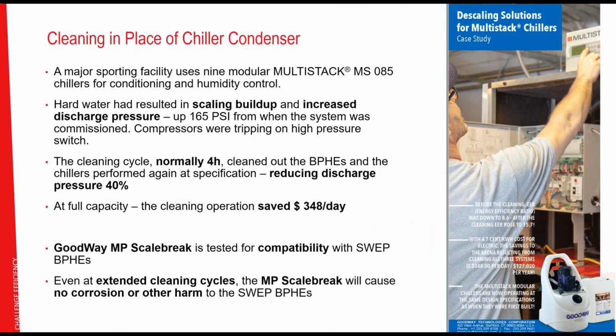One of the case stories that we did together was with a mutual customer, Multistack Chillers. And this case here was a sporting facility somewhere in the south, which had a Multistack MS85 chiller, or quite a lot of them. What they noticed was that the compressors were tripping on the high pressure switch. That's normally not the case. That shouldn't happen, right? So they did a measurement and they saw that the discharge pressure was up 165 psi from when it was originally commissioned. And I don't know how much you know about refrigeration systems. That's a lot, right? Especially if the compressors start to trip as well.